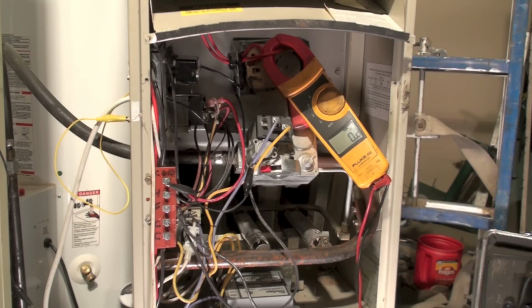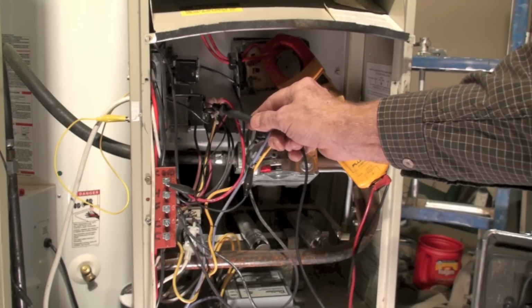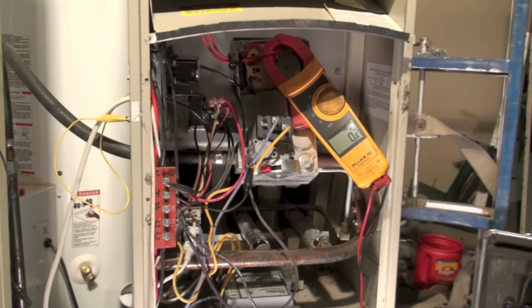A breaker may show on. I would turn it off and then turn it back on again just to make sure. And it should be a dedicated breaker. A dedicated breaker simply means a breaker that is dedicated only to the furnace. Minimum of 15 amps. So, no power, start looking back through the power system, find out where the power has failed. This will almost certainly be 120 volt power. You could have a transformer problem like right here, and you'll have to check input and output on a transformer.